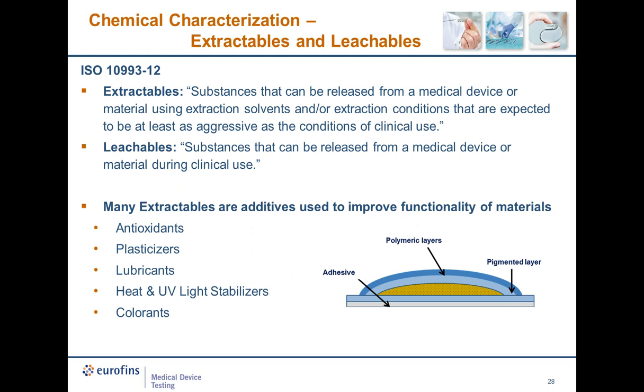Extractables are compounds that can be released from a device under conditions that are at least as aggressive as typical use. Leachables are compounds released from a device during actual clinical use. Because the conditions used to generate extractables are harsher than clinical use, typically leachables are a subset of extractables. Both extractables and leachables are all-encompassing terms to describe many different compounds from many different potential sources with many potential different risk factors. Evaluating the potential extractable or leachable compounds is the final endpoint for chemically characterizing a device.